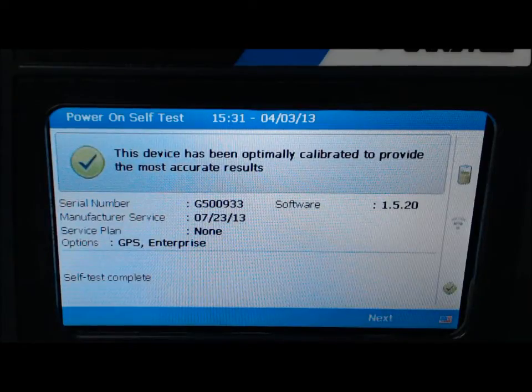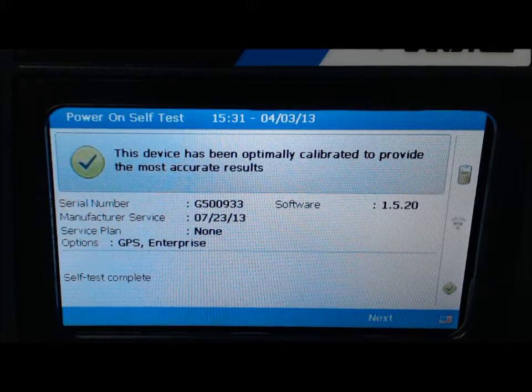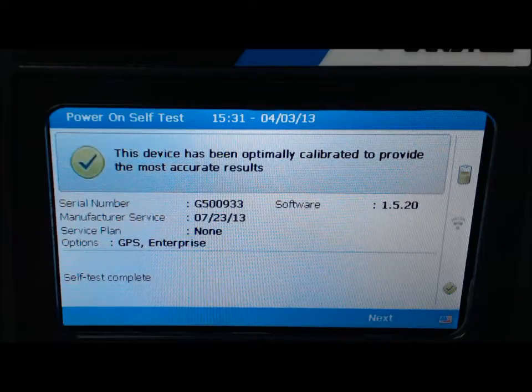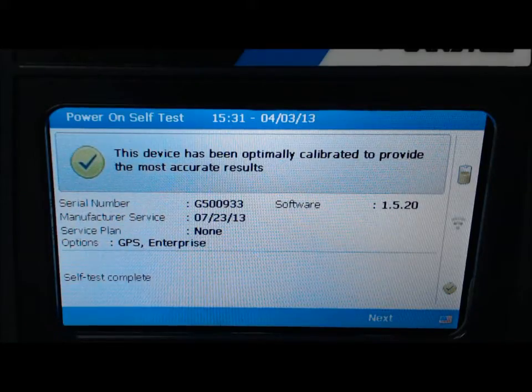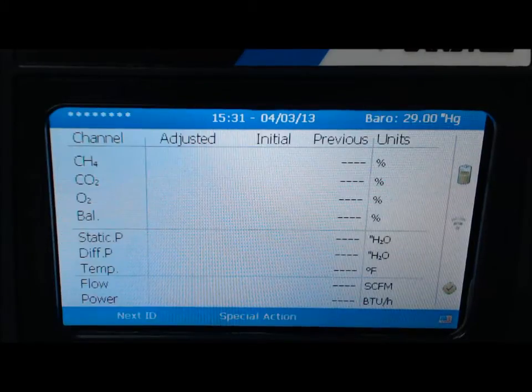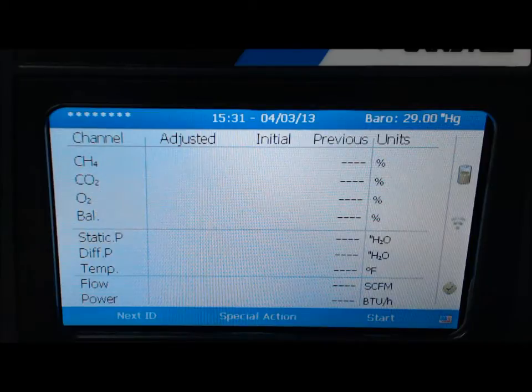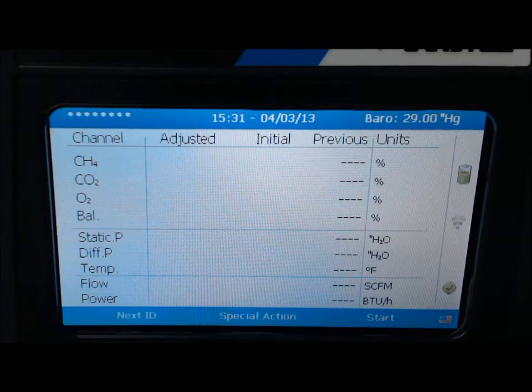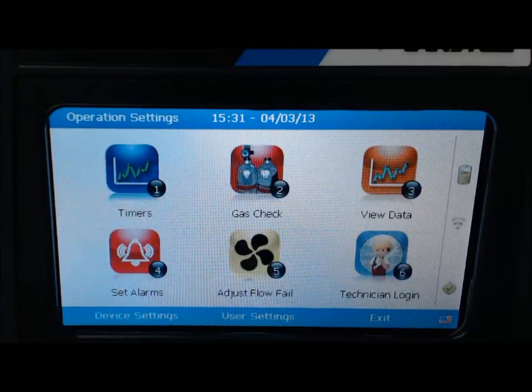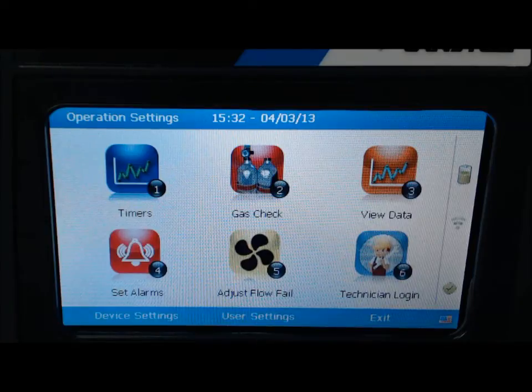Welcome to the GEM 5000 training video for field calibrating your instrument using software version 1.5.20. After the startup screen, select next. You will be taken to the reading screen. From this screen, select the menu key. This will take you to the operation settings screen.